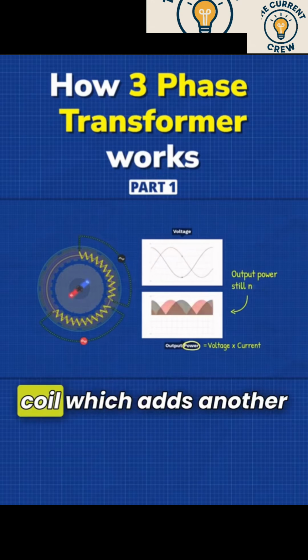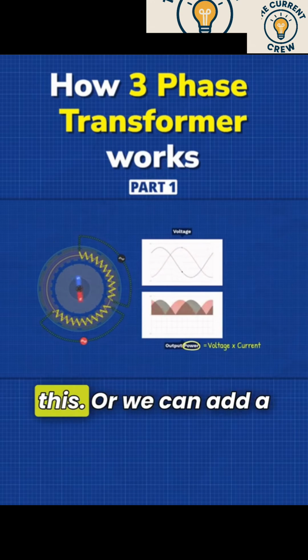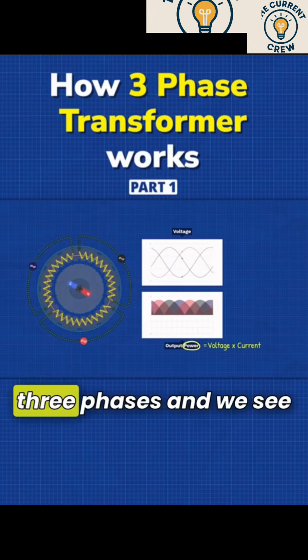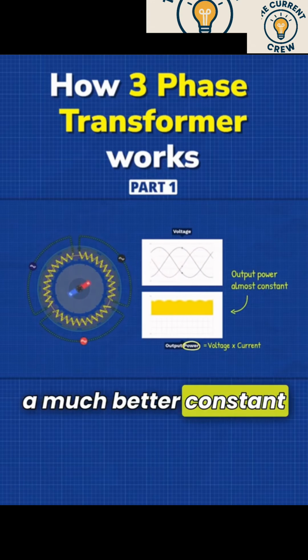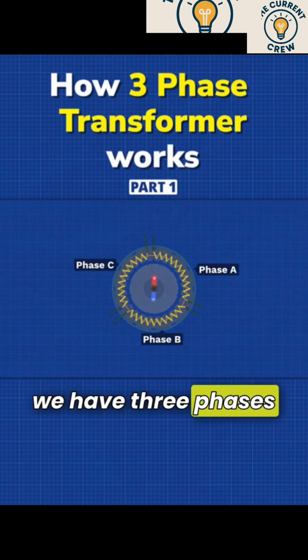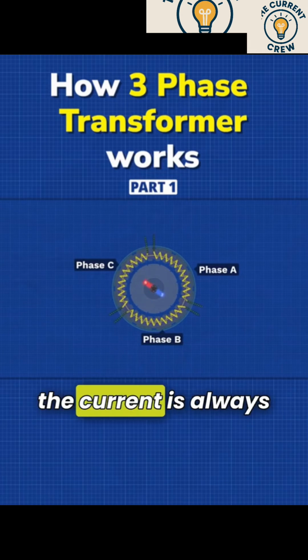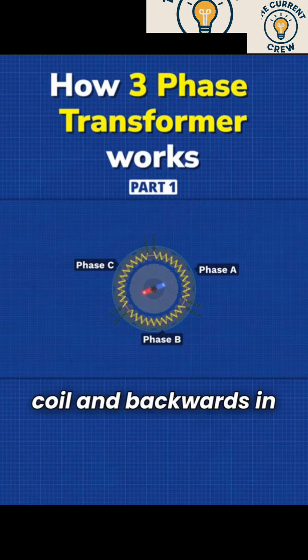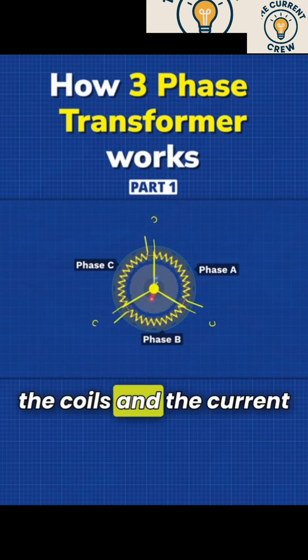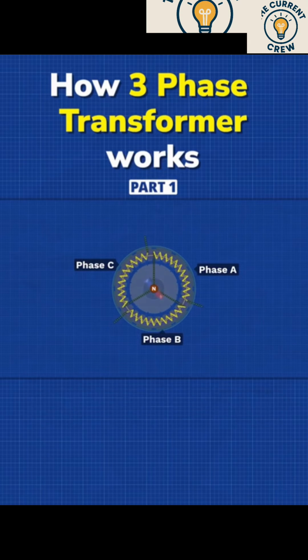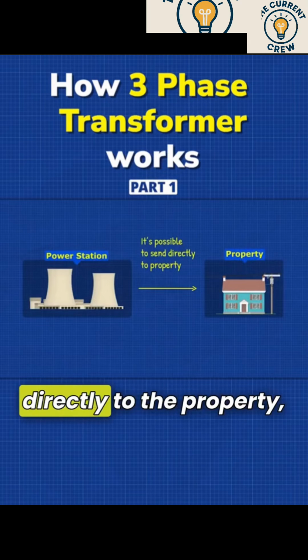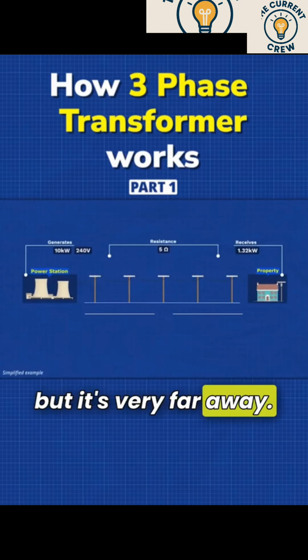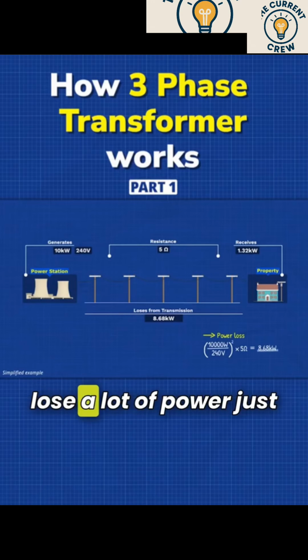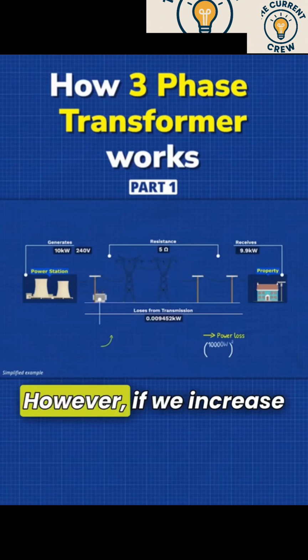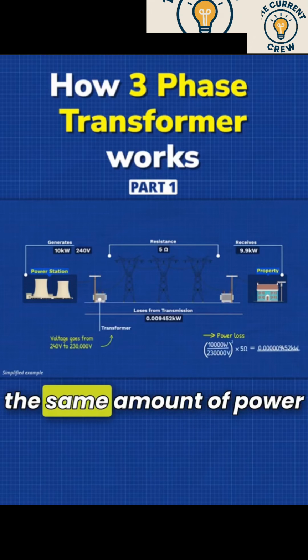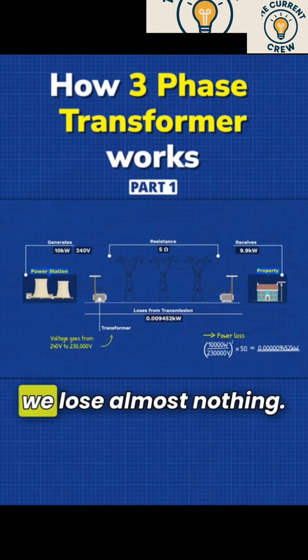We could add another coil which adds another phase and helps to improve this. Or we can add a third coil giving us 3 phases, and we see a much better constant output power. Notice we have 3 phases but 6 wires. Also notice the current is always flowing forwards in one coil and backwards in another. So we can combine the coils and the current will share the wires, only using them when they need to. We could try sending this power directly to the property, but it's very far away. So the resistance of the wire means we will lose a lot of power just trying to get it there. However, if we increase the voltage, we can send the same amount of power with less current. So we lose almost nothing.